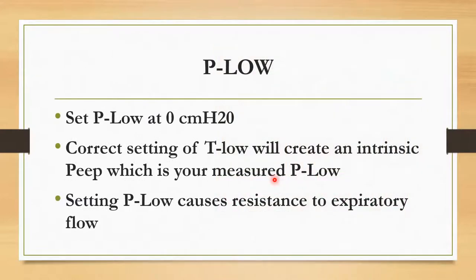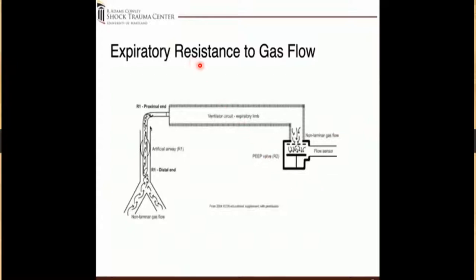As mentioned, the P-low is set at zero. The correct setting of your T-low will create an intrinsic PEEP — your measured P-low. If you set the P-low at 5–10, this causes resistance to expiration. There's flow resistance through an exhalation valve and PEEP devices. Setting a P-low value forces gas through the expiratory valve, restricting flow. Since these releases are super brief, you want the best gradient — releasing P-high to ambient air creates the largest gradient and does not restrict flow. This produces very rapid release followed by return to P-high.